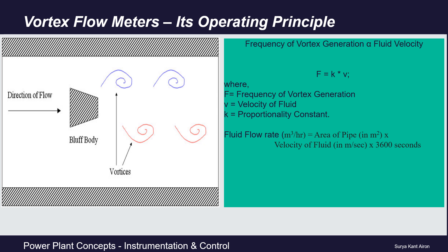Here F is the frequency of vortex generation, V is the velocity of the fluid, and K is a proportionality constant. Once we measure this fluid velocity, the fluid flow rate can be easily calculated because fluid flow rate equals the cross-sectional area of the pipe multiplied by the velocity.